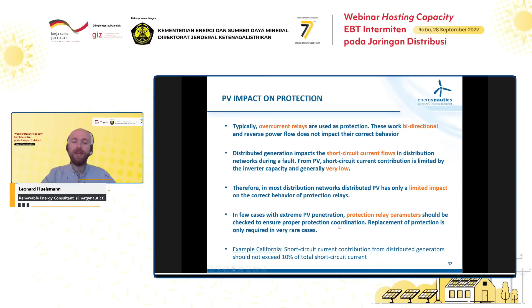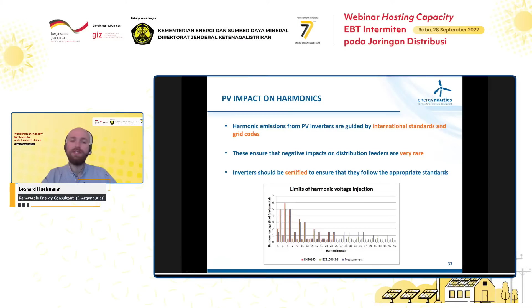We have also impacts on harmonics, and this is typically guided through international standards and grid codes, where certain restrictions are put on the harmonic content from PV inverters. And also this, like having actual negative impacts on distribution feeders, is a rather rare phenomenon. However, it needs to be ensured that your PV inverters are certified and checked according to the appropriate standard, so that good equipment is used in the distribution network.